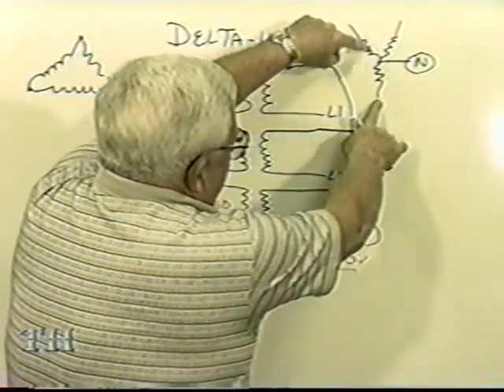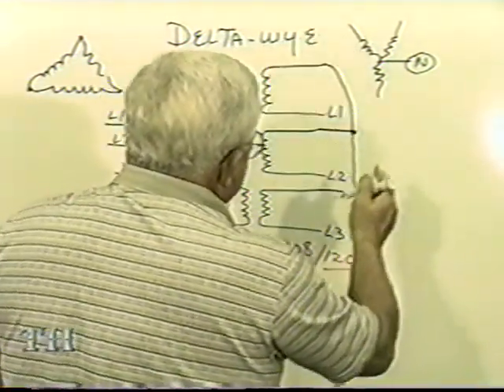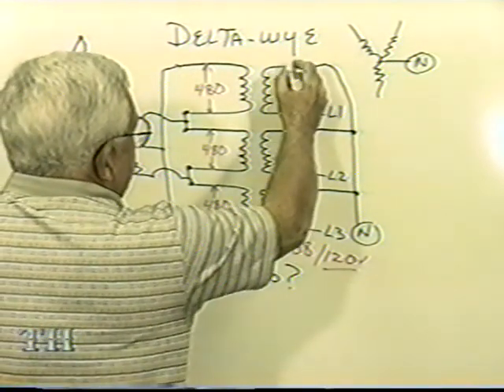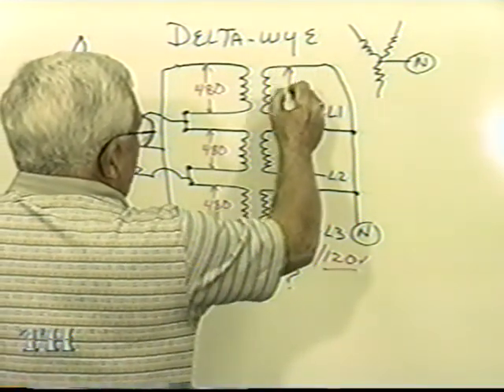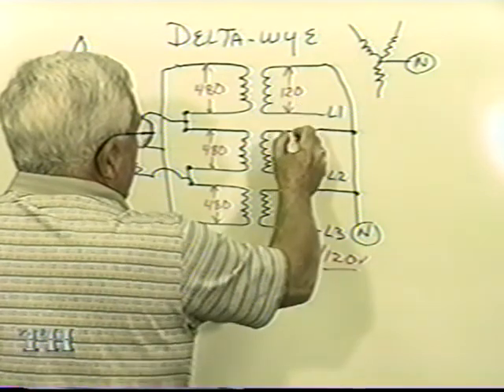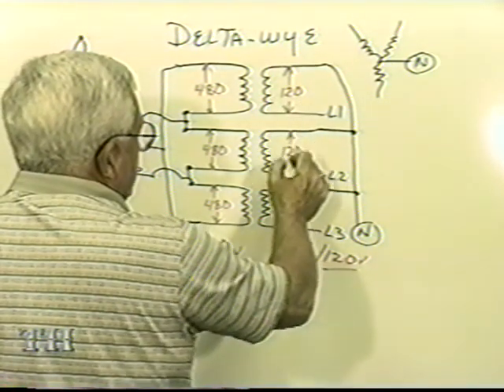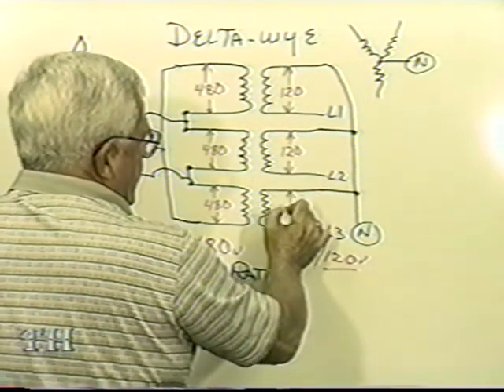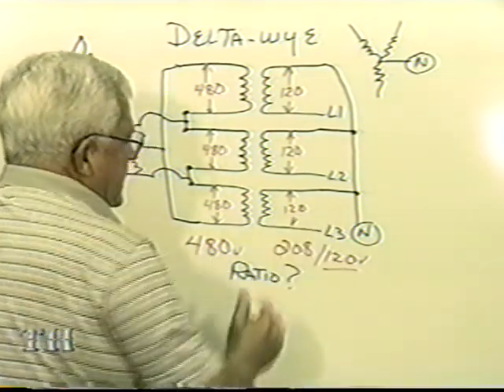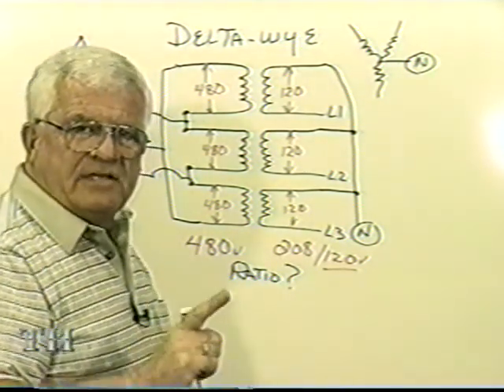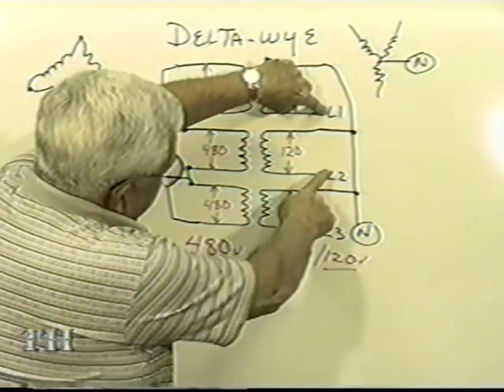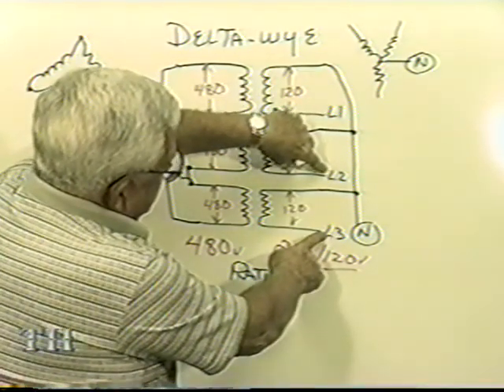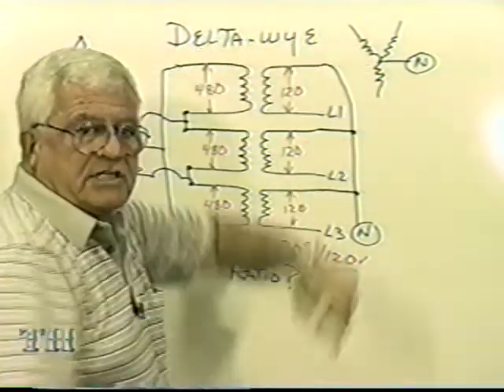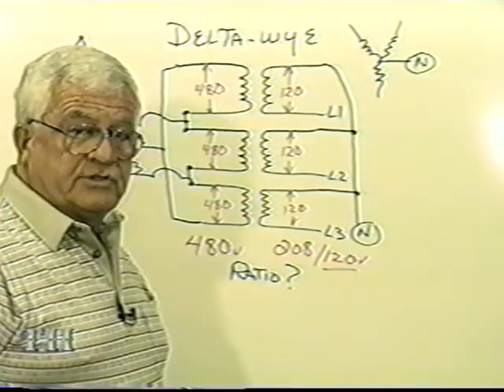If you say from here to here, it's 120 volts, you're putting your meter right here. 120, 120, 120. See, the 208 volts, that's a line voltage. 208 is from here to here, and from here to here. See, line voltage, you're actually reading across two coils, two phases.